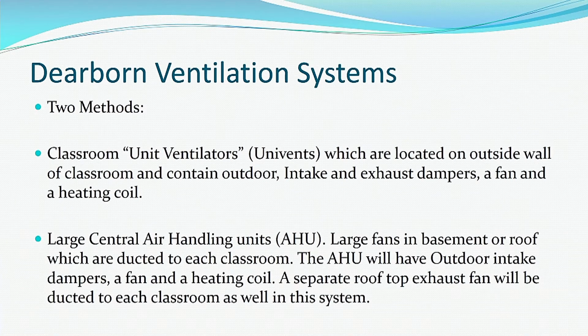Many of our schools, instead of unit ventilators, will have large central air handling units or AHUs. And that would be a large fan in a basement or a rooftop that would be ducted to several classrooms. And of course, that fan unit would have heating coil and a duct to the outside. So with an air handling unit, that would be an alternative to a univent where we would have a large piece of equipment that would bring in outdoor air, heat or cool it as necessary, and deliver it ducted to multiple classrooms. And that system as well would have large exhaust fans ducted to all those classrooms. So we would have an air handling unit delivering fresh air and an exhaust fan exhausting the stale air, operating in all our classrooms and spaces while the building is occupied.